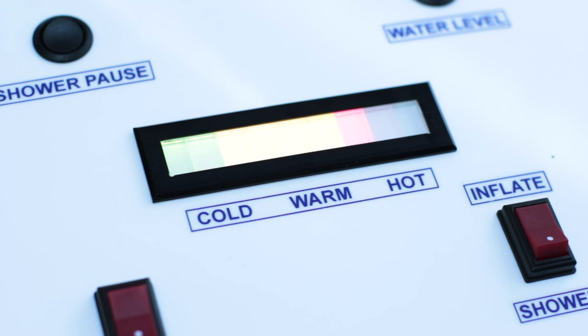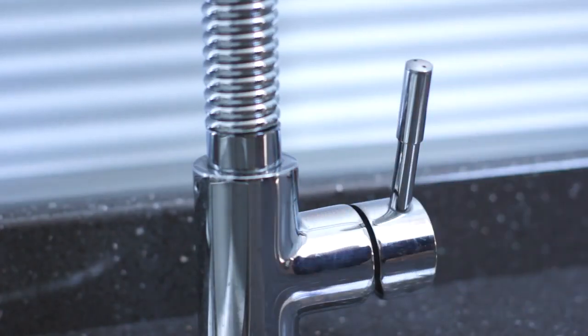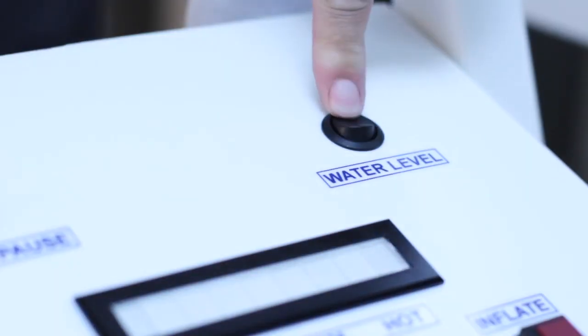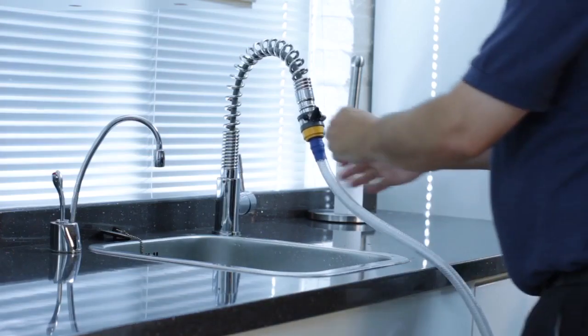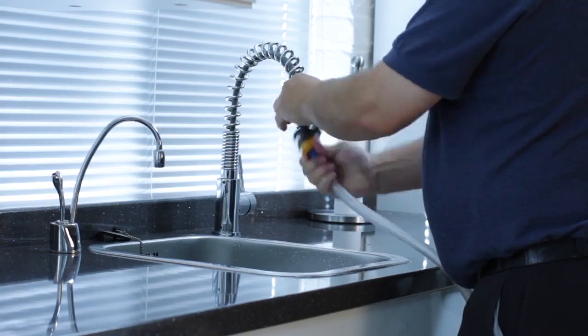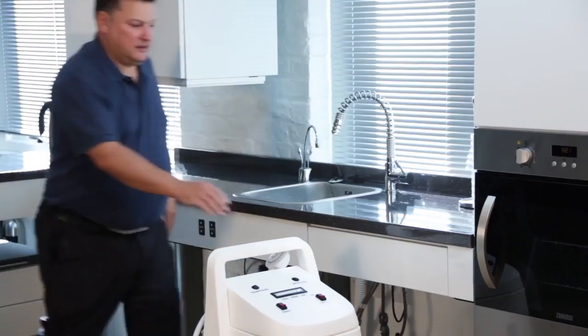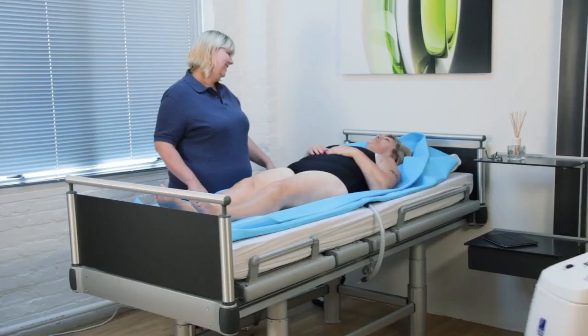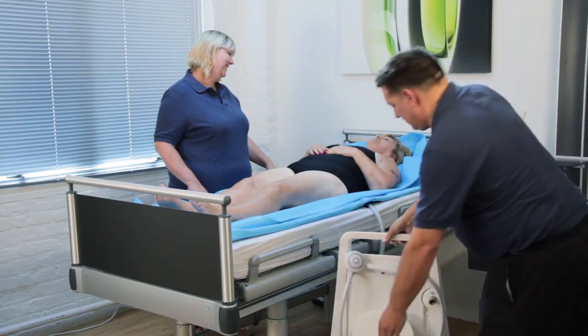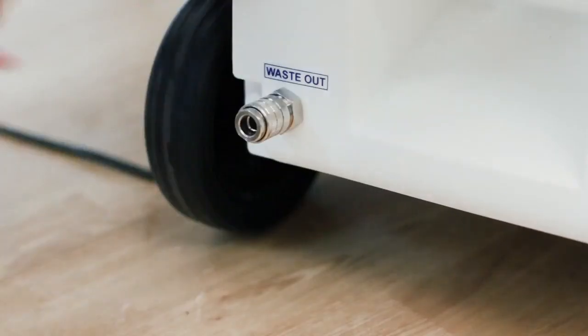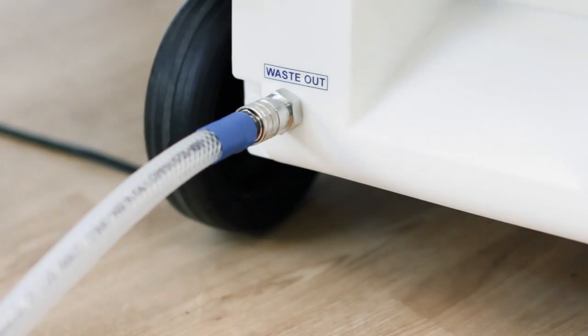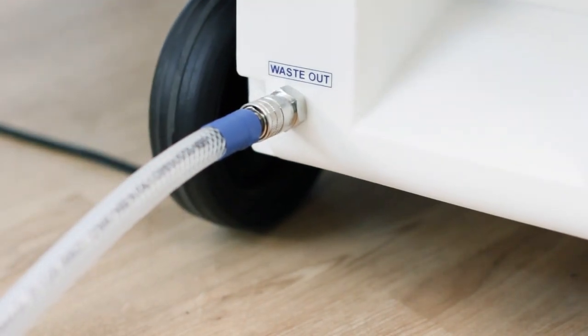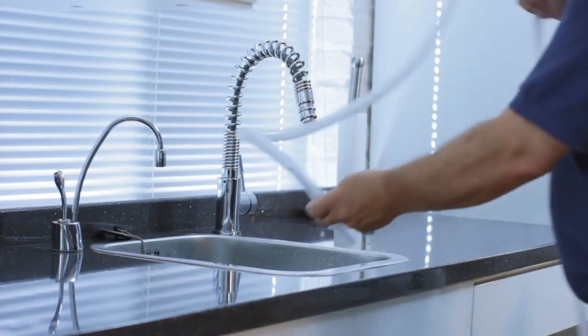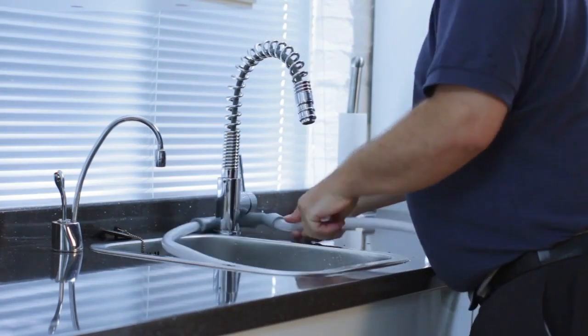Once the tank is full, the beeping will change to a constant note. Turn off the water taps. Press the water level button to turn off the bleeper. Disconnect the tap hose, unplug the mains plug, wheel the Water Genie to the patient's bedside and plug into a plug socket near the bed. Connect the waste out hose, which has no filter, to the bottom left-hand socket of the Water Genie and place the other end in a convenient drain.